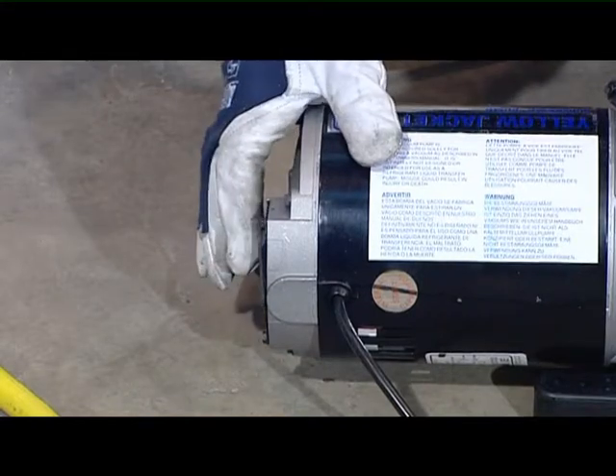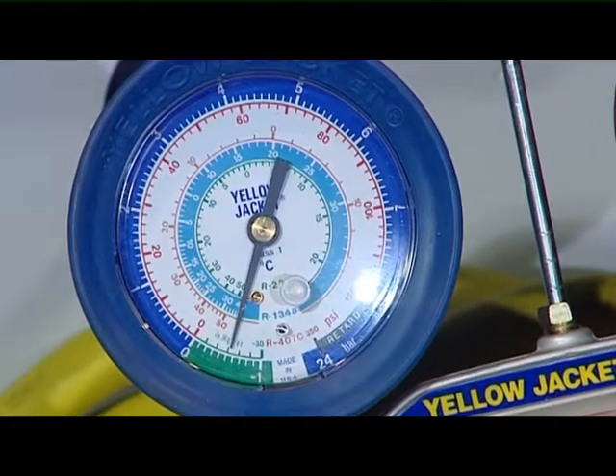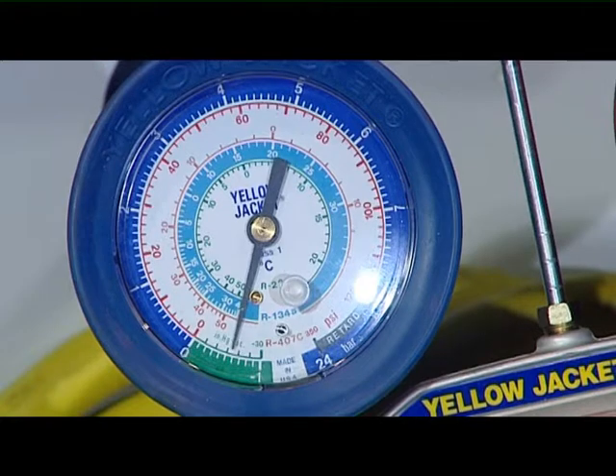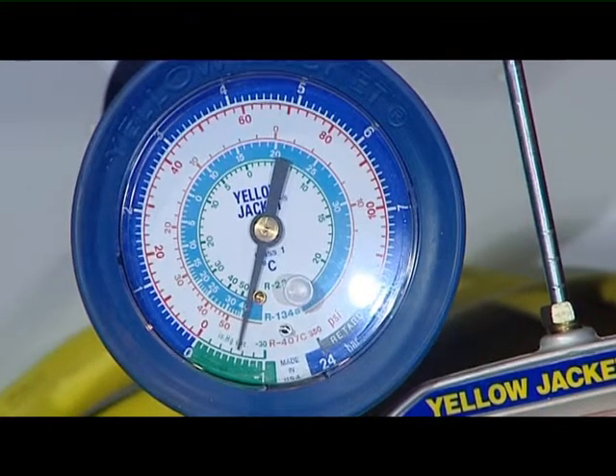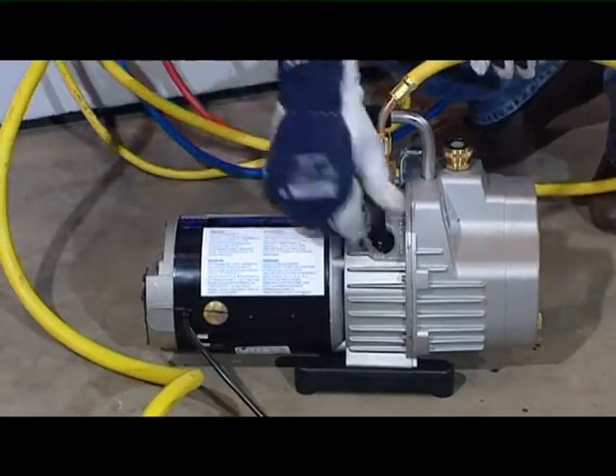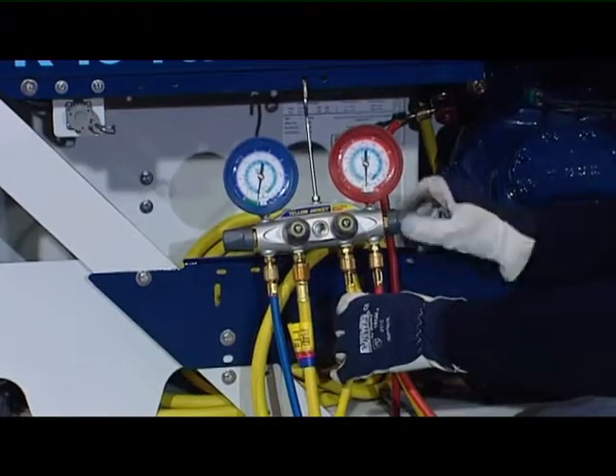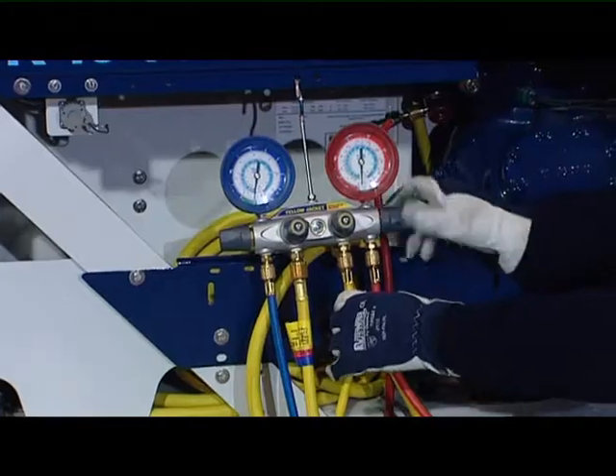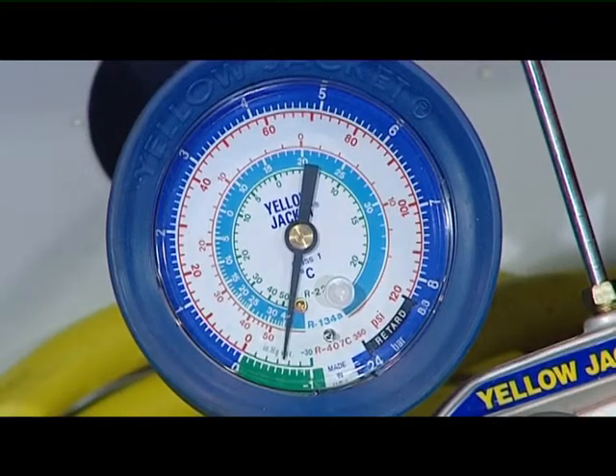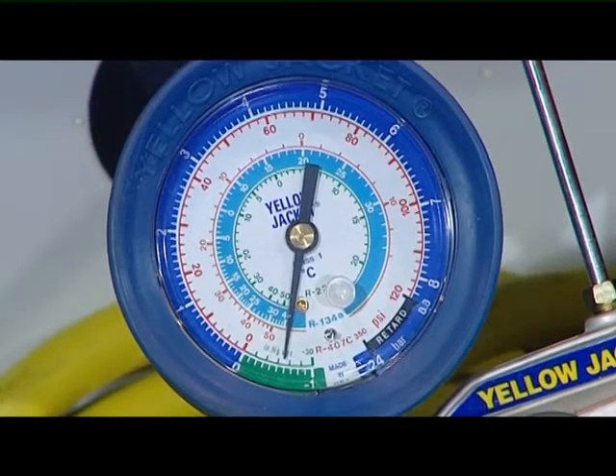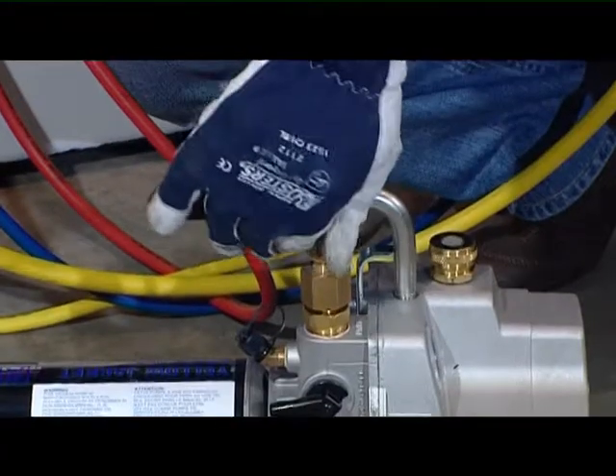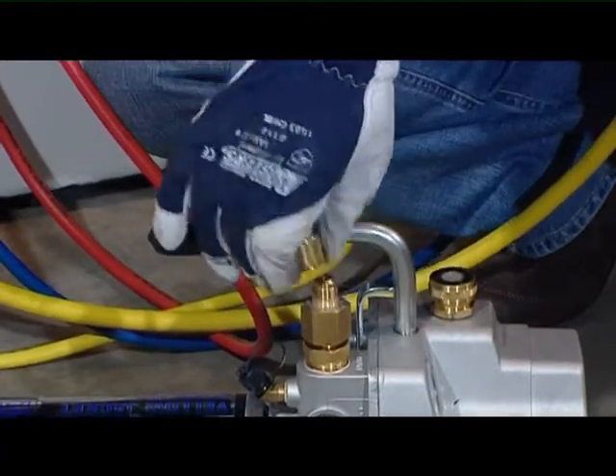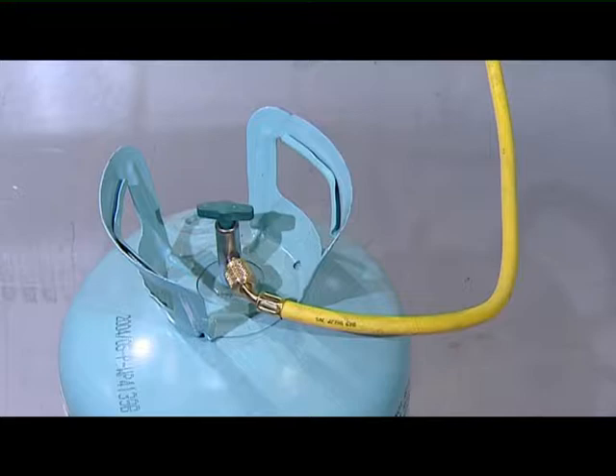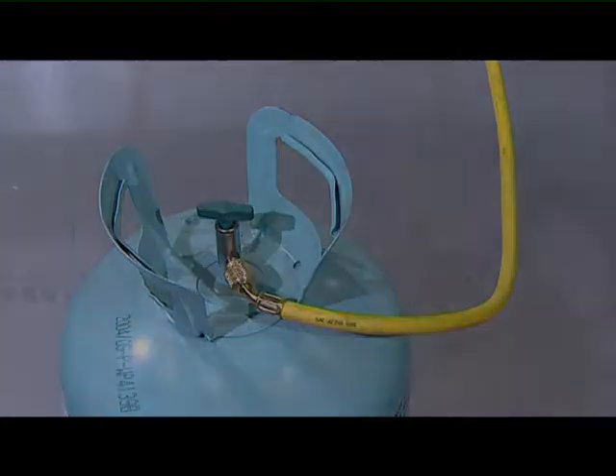Start the vacuum pump. Evacuate the system until a deep vacuum is reached, as can be read on the manifold. Switch off the pump. Close all the hand valves on the manifold and see if the vacuum holds. Wait to check if there is residual moisture or leaks. If the vacuum holds, the pump can be disconnected and the system is now ready to be filled with a new charge.